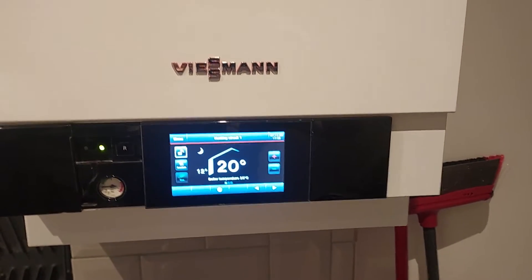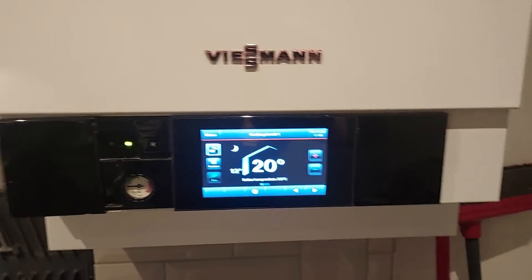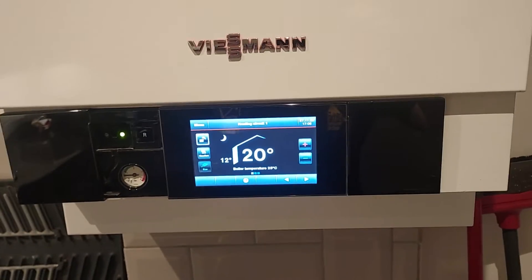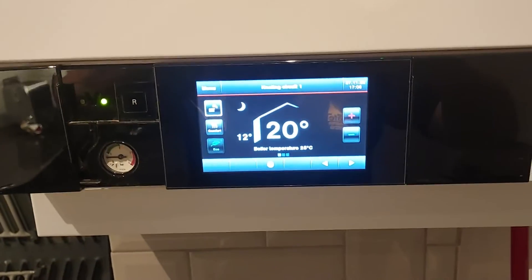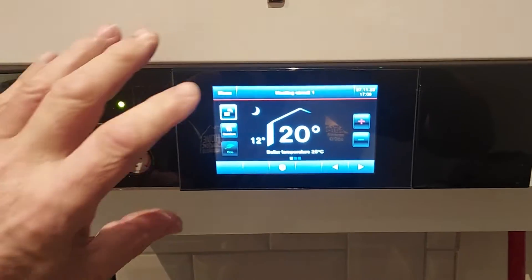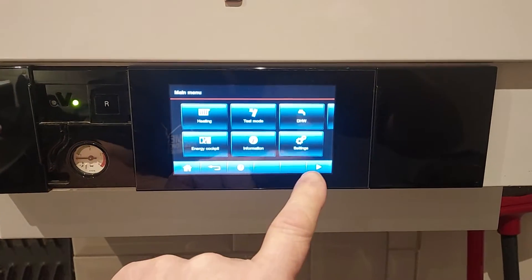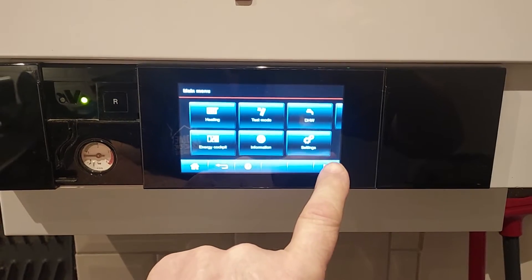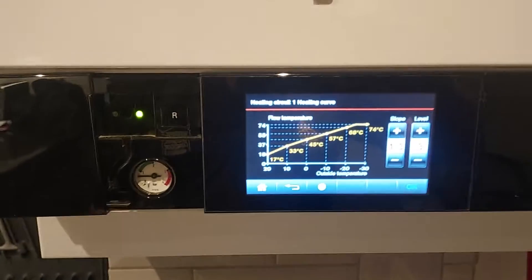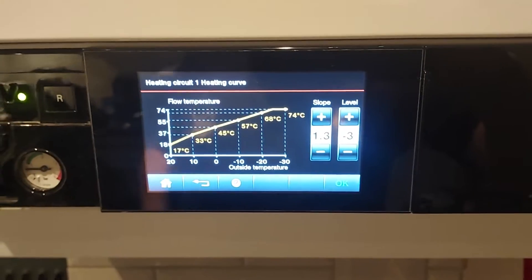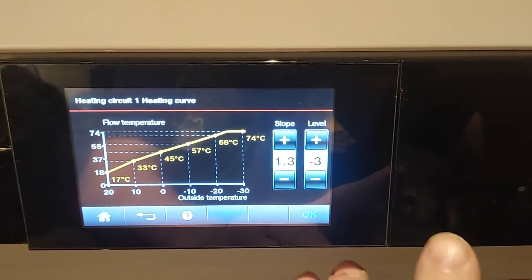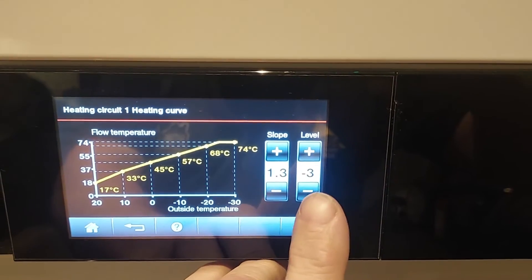A video for Andrew Alderton. I'm just talking about the weather compensation controls on the Viessmann 200 and the ability to adjust the level as well as the slope. So if we go into heating and we go into heating curve, we see here we've got two parameters we can adjust in the settings — the slope and the level.